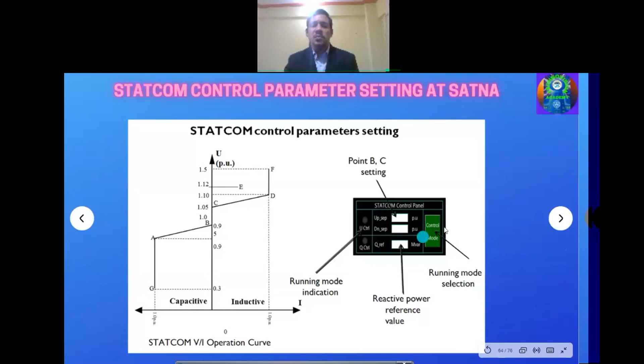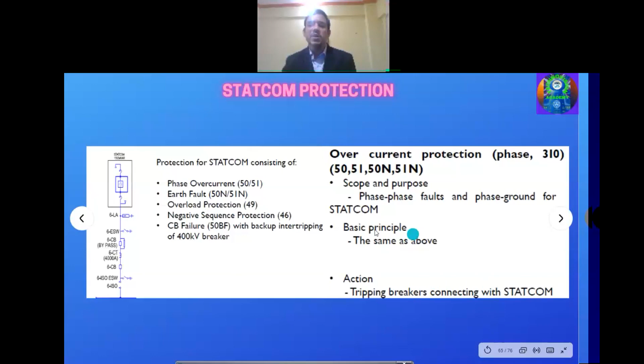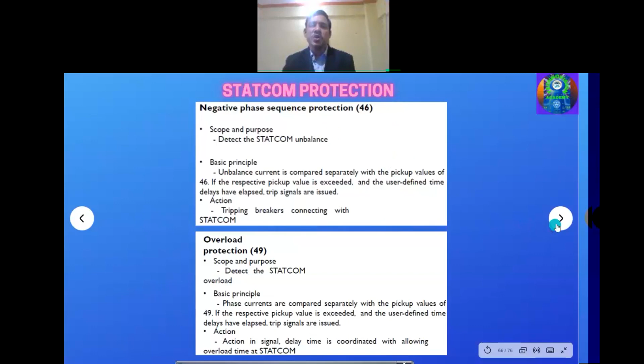Again, some protections are also needed for the STATCOM. We have to protect it. For that, we provide certain relays like overcurrent protection, different relays 50, 51, 50N, 51N, meaning overcurrent and earth fault, overload protection, negative sequence protection, and CB failure protection. All these protections we have to give for the STATCOM, along with tripping of the breakers connected to the STATCOM. The breaker connected to the STATCOM should be tripped when such faults are sensed by these relays. Again, negative phase sequence protection is also given. Overload protection: if there is an overload of the capacitor bank, then this protection will operate. Negative phase sequence components come because of unbalance in the system, so this protection will take care of the STATCOM.